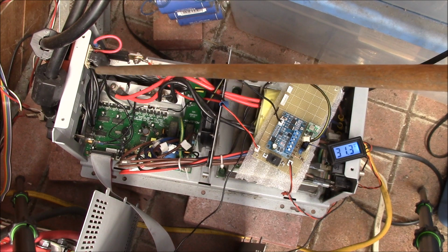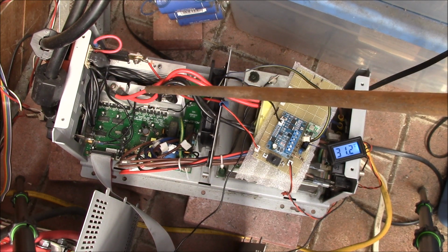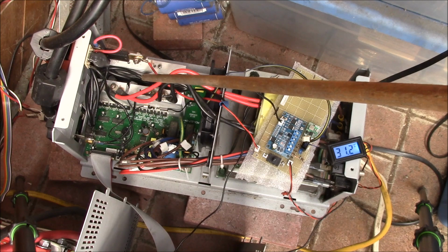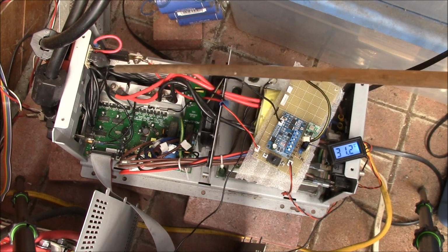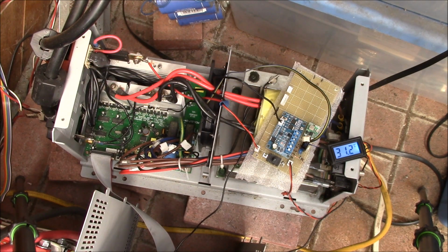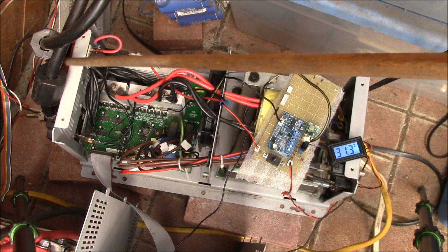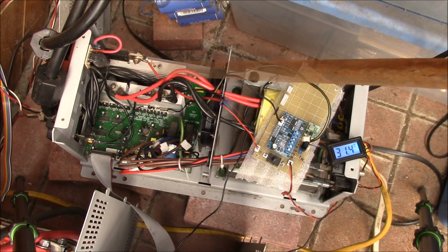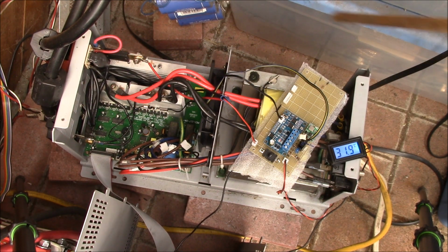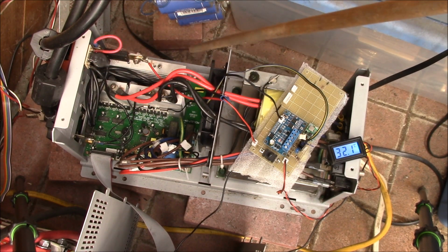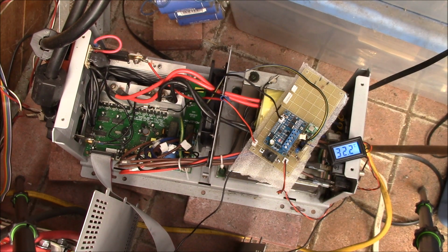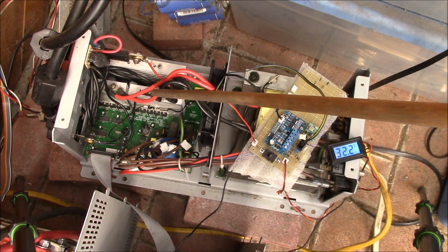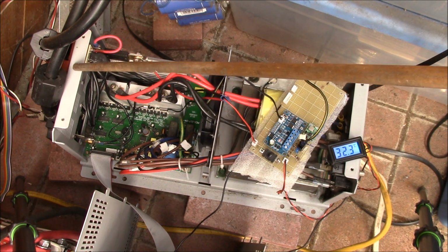It just brings power in and sends it right back out, and it also charges the batteries. If the battery voltage had dropped while running on battery power, it uses this same circuit to pump current back into the batteries and charge them up. This is basically a UPS, but you can add whatever size battery you want, so that's why they call it an inverter - it takes DC power, inverts it into AC power, and sends it out this wire. But it can also take AC power in, convert that to DC, and charge the batteries.